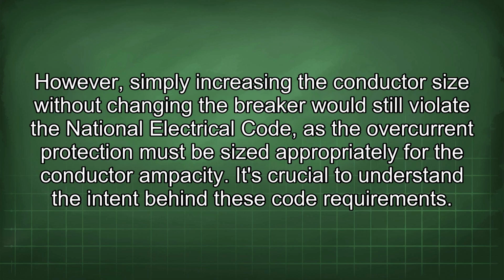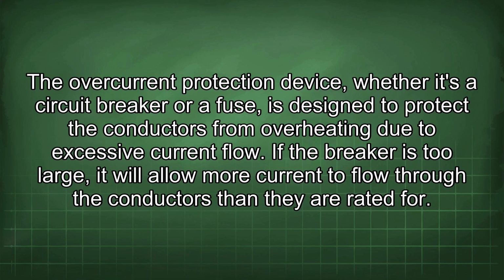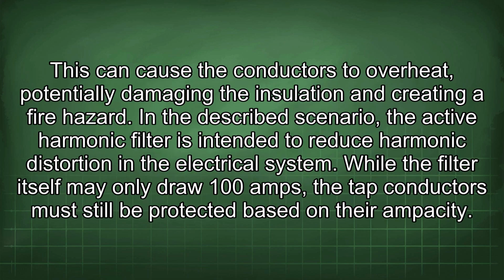However, simply increasing the conductor size without changing the breaker would still violate the National Electrical Code, as the overcurrent protection must be sized appropriately for the conductor ampacity. It's crucial to understand the intent behind these code requirements. The overcurrent protection device, whether it's a circuit breaker or a fuse, is designed to protect the conductors from overheating due to excessive current flow. If the breaker is too large, it will allow more current to flow through the conductors than they are rated for. This can cause the conductors to overheat, potentially damaging the insulation and creating a fire hazard.